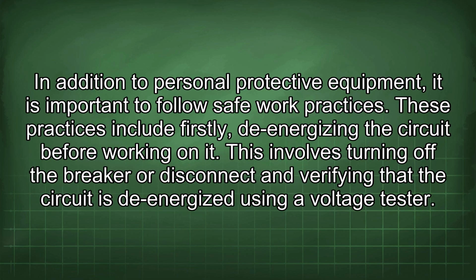In addition to personal protective equipment, it is important to follow safe work practices. These practices include firstly, de-energizing the circuit before working on it. This involves turning off the breaker or disconnect and verifying that the circuit is de-energized using a voltage tester.